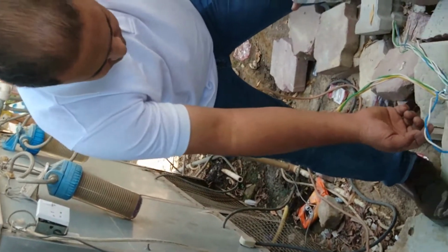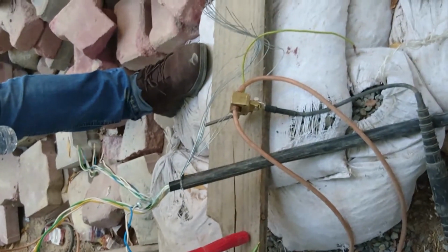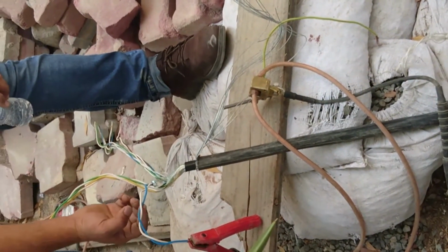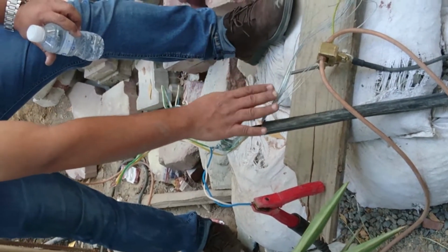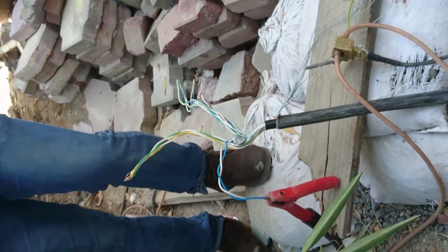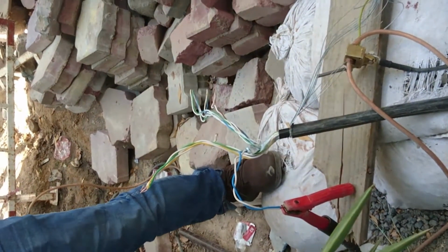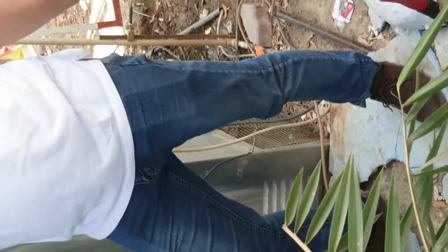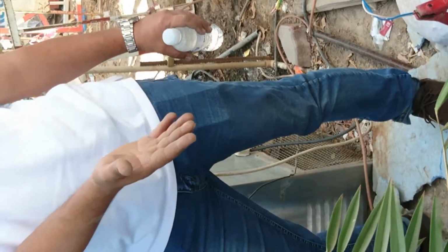Let's assume we have a problem. I just made the connection double to make it easier; you can also connect one on one string. So white and blue and armor. We will make a fault at the end of the cable between these two cores. Now it's open over there. We will stop the testing, doing only a high voltage test to see if maybe there is another problem in this cable, somewhere here, not only at the end. We will give a maximum voltage, the capacity of this cable.